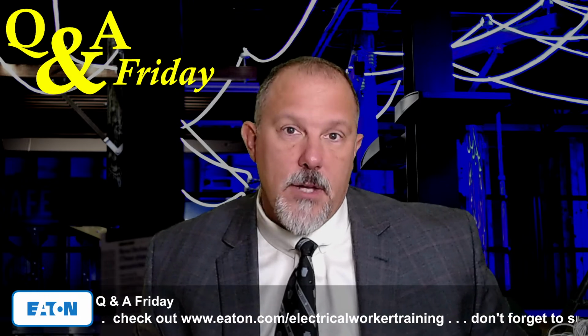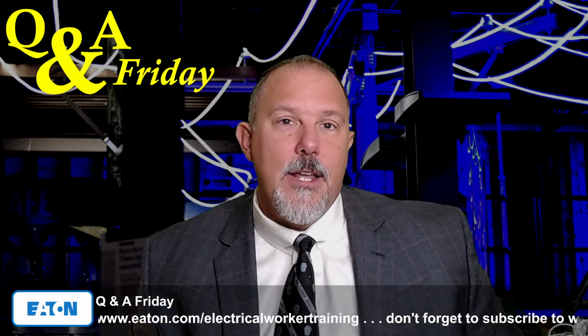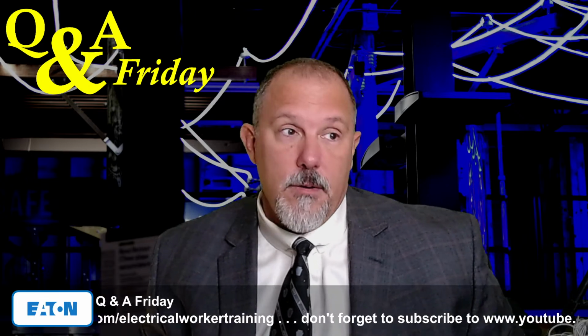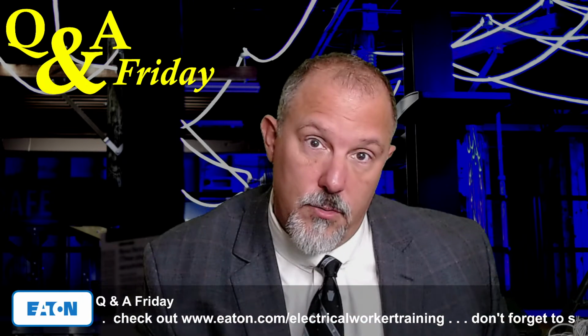And I recall years ago talking to an electrical inspector, a very good electrical inspector, who had an installation where they had a 3-phase panel used in a single-phase application. And he called me with the exact same question, and together we could not find anything in the NEC that would prohibit that installation. I'm not exceeding any ratings. I'm not exceeding the rating of the bus from an ampere value. I'm not exceeding the rating of the bus from a voltage value. I have an unused bus bar, but so what? There's nothing in the code that says you have to use that bus bar.